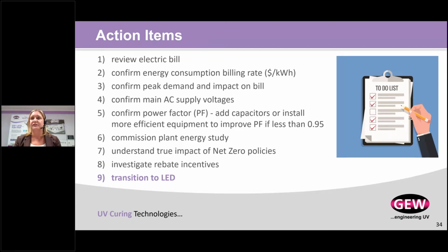What are your AC voltages? Just because the generating plant is providing you with 480 volts, it may be that you're pulling 490 or 500 off the line. If you are, you need an internal step-down transformer to bring that down, because you're tearing your equipment up by running at high voltages.